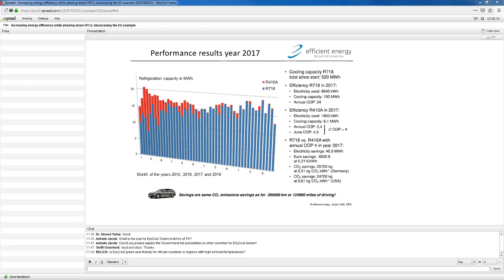If you look along the line, then the bars shown there, they get more and more blue, meaning they use basically only our system, the water system, and then they used the R410A system more or less only as a backup. If you look at the year 2017, then we had an annual efficiency of COP 24.